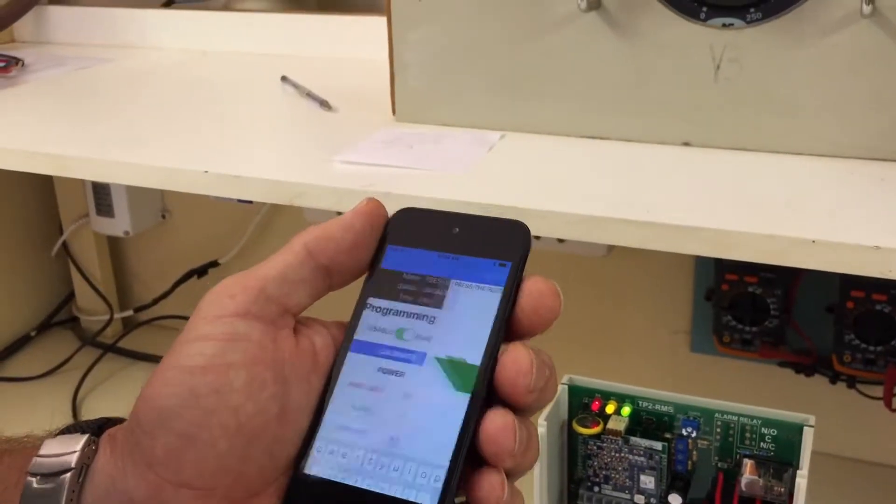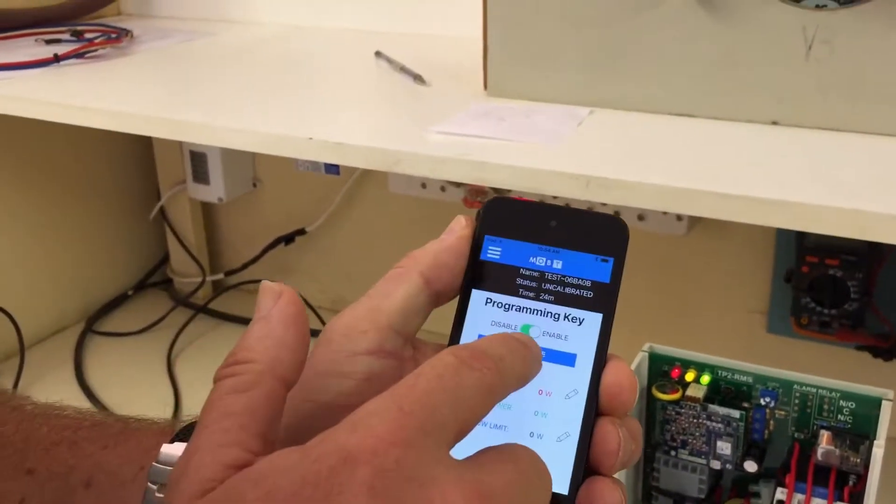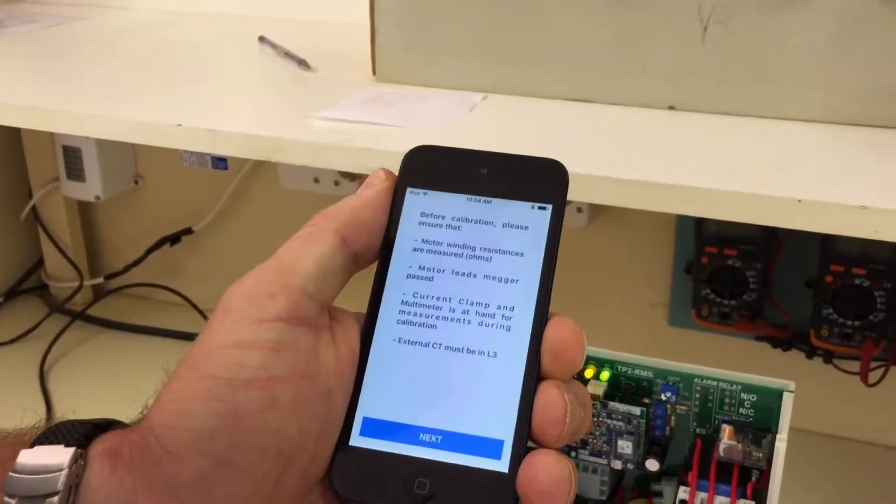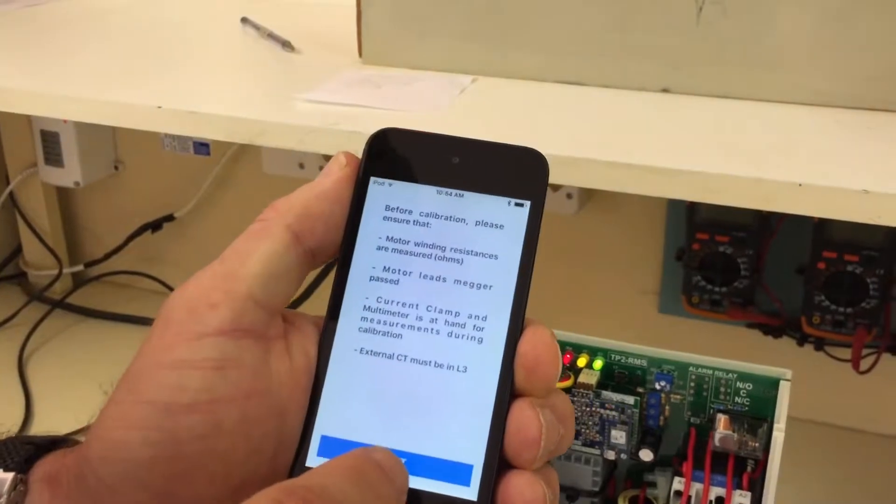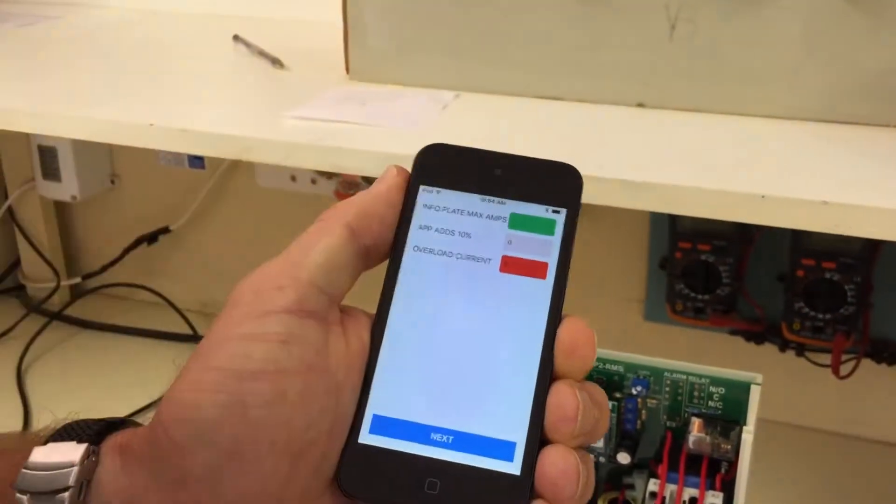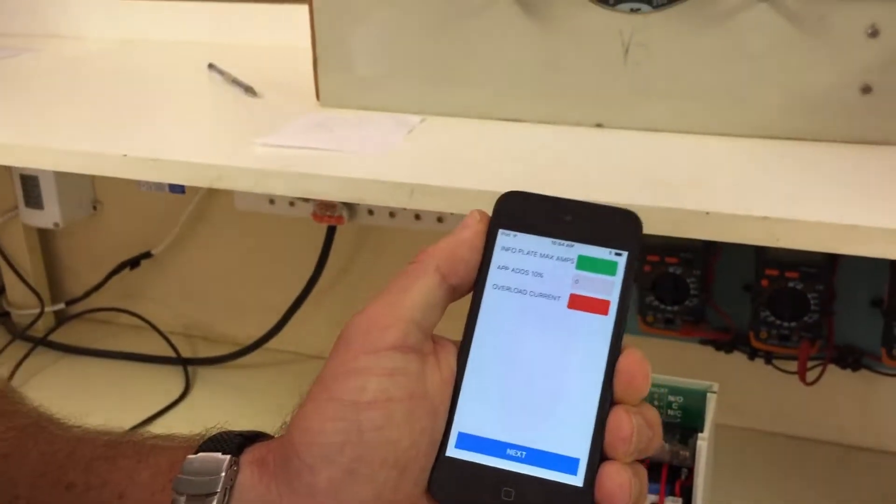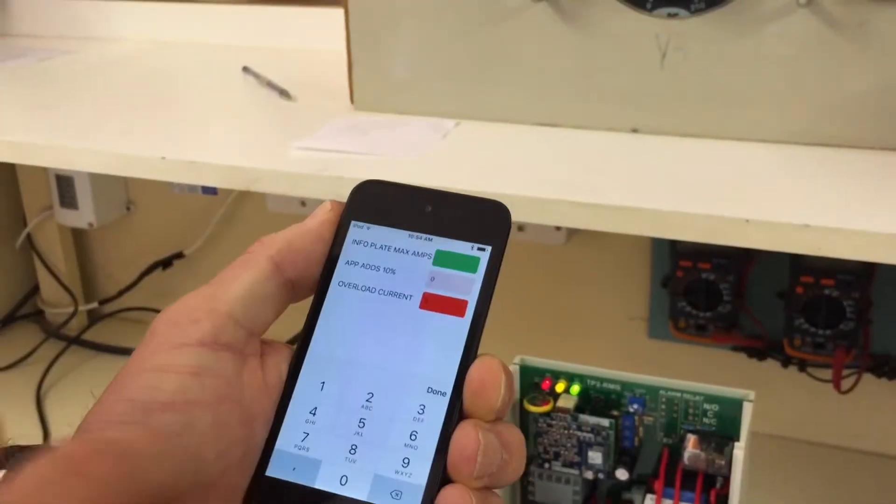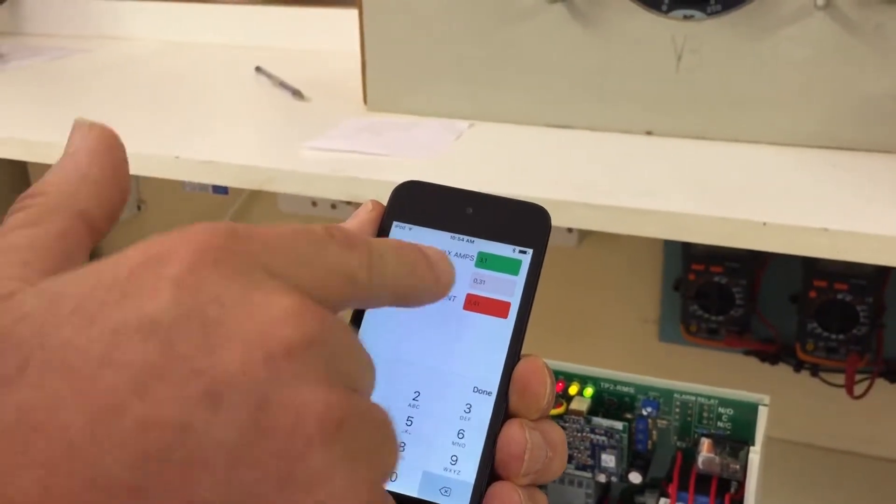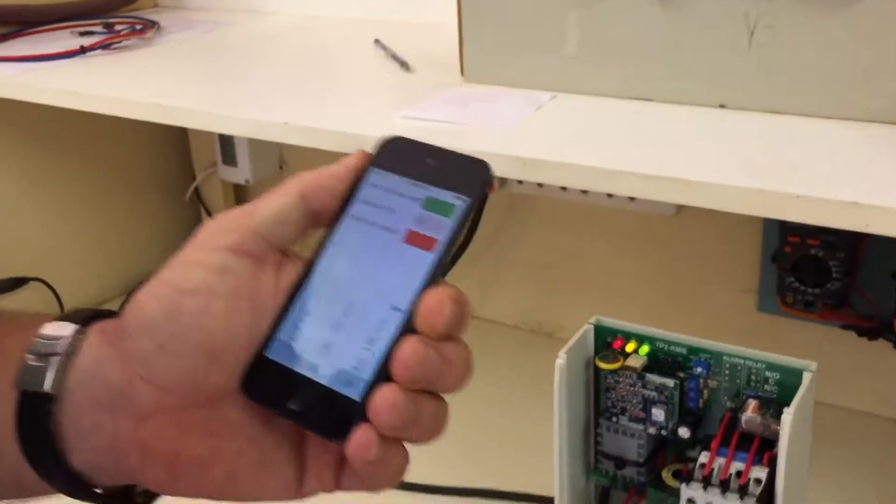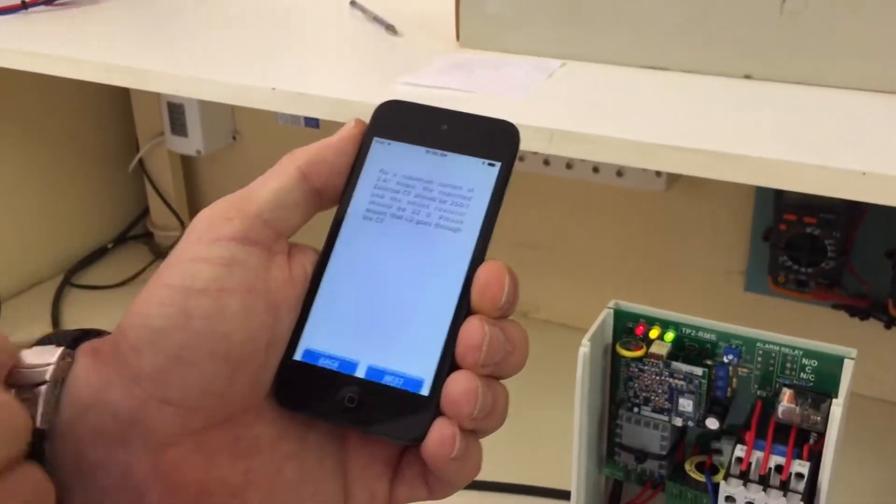Press the button and then we can give it a name. Okay, this is for the journal that's going to be created, calibrate. This is all the things that you need to have with for a safe calibration. Next, and then it requests the maximum amp on the info plate of the motor. Okay, we'll add the 3.1, you can see 10% is already added. The motor is allowed to draw 3.1 amps, so we need to give a bit of a gap. Done, next.